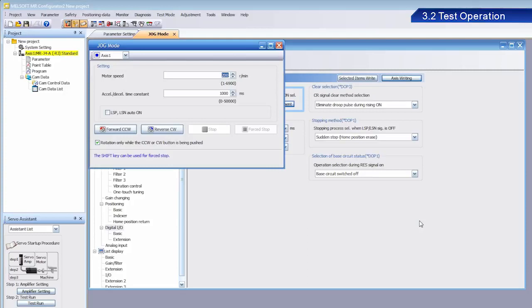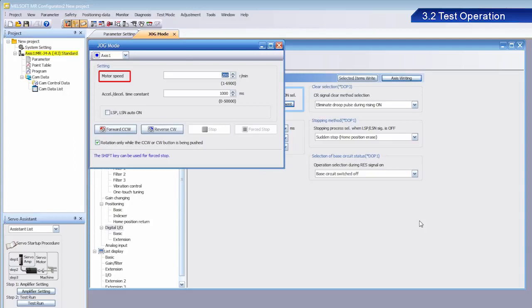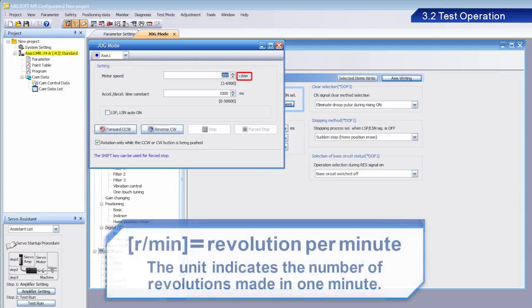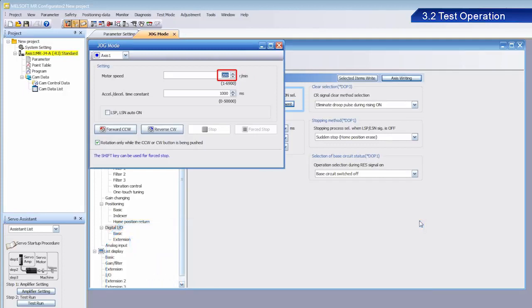The jog operation screen appears. At this time, set the values for motor speed and acceleration-deceleration time constant. Motor speed sets the rotational speed of the servo motor. The unit of measure is r per min, which is an abbreviation for revolutions per minute. Entering a value of 200 sets the motor to rotate 200 times per minute.